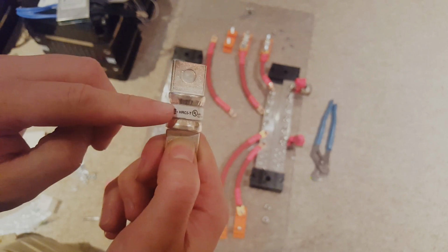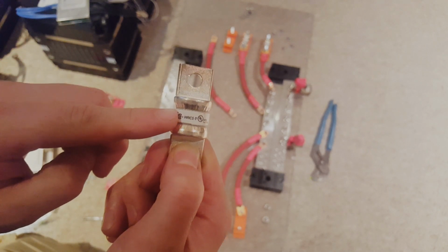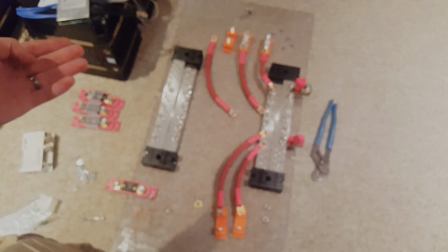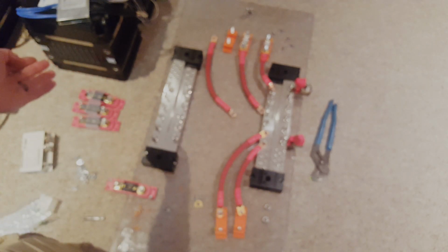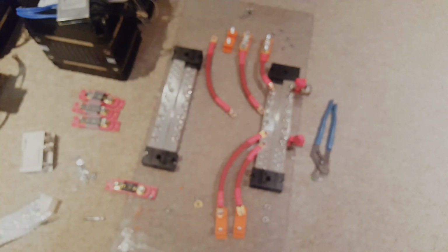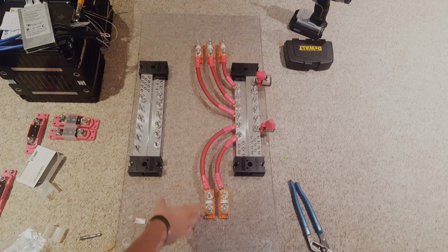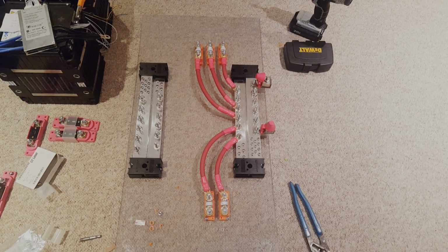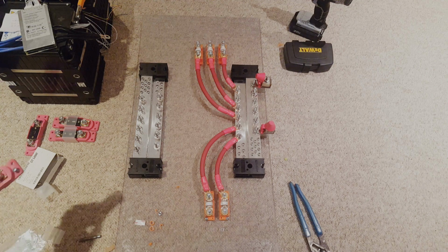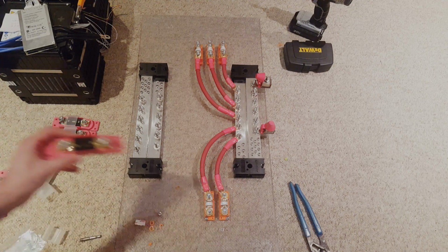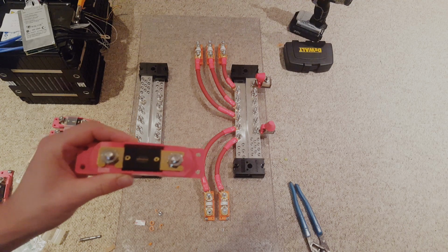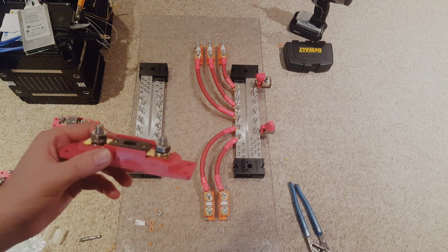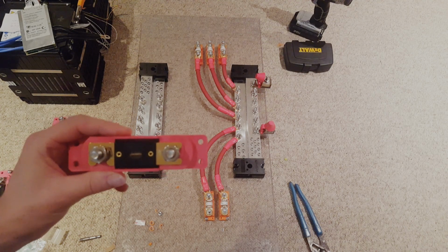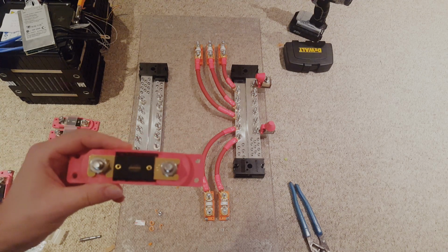So it's really important to use the correct type of fuses for this application, because even though lithium iron phosphate is a safer battery chemistry, you can still run into issues with the wiring or the fuses that you decide to use. Alright, so now we have all the Class T fuses installed. It didn't really take that long, and the safety factor of this is well worth it, because honestly guys, if you're gonna do this, these are probably the one thing you do not want to skimp on. And you can see we bought high quality fuses to begin with, but they weren't correct for this application.